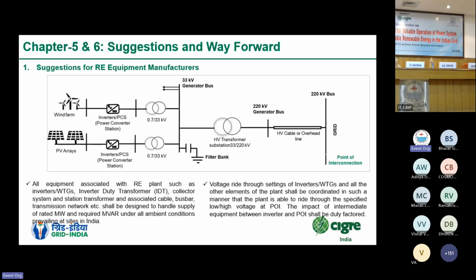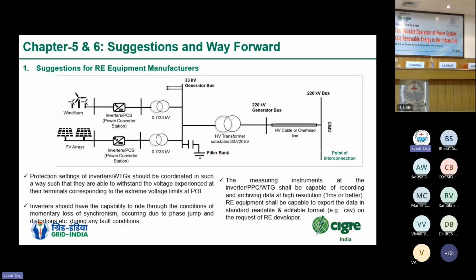So this was one of the major findings. Another is that in this complete setup, we can see a lot of electrical equipment. There is the 220 kV bus, the 33 kV bus, and again a 700 volt system. All these have their own sets of protection systems. So it is very important that all sets of protection systems are coordinated in such a way that, in their simultaneous operation, they are able to display the desired features and desired performance at the point of interconnection.